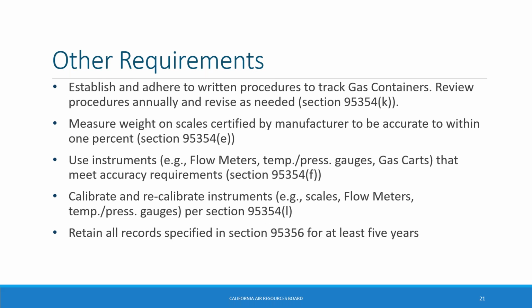Here we've listed a number of other requirements GIE owners should be aware of. First, section 95354K requires GIE owners to establish and adhere to written procedures to track gas containers. Per section 95354E, scales used to measure weights must be certified by the manufacturer to be accurate to within 1% of the true weight. Flow meters, temperature and pressure gauges, and gas carts must meet the accuracy requirements in section 95354F.